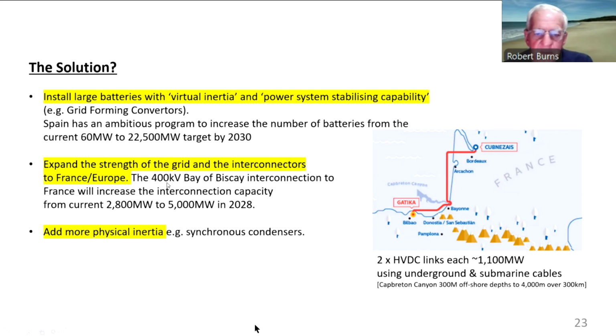And there is an interconnection project. It's called the 400 kV Bay of Biscay interconnection, and that'll increase the interconnection with France from the current 2,800 to 5,000 in 2028. And you can see this little diagram here. This is the Pyrenees here, a little place called Bilbao. There's a substation Gatica, and you can see the high voltage DC link up here to France near Bordeaux.